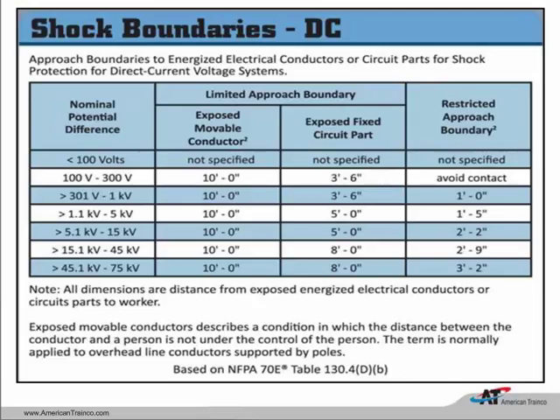And these are both shock protection tables. They have been revised a little bit, especially the biggest one that got taken out was the prohibited approach boundary. Completely gone because it didn't trigger anything. Remember that limited approach boundary triggers no unqualified people. Restricted approach boundary triggers we're going to have all of our PPE on, 1,000 volt rated tools, and the right category of meter. So both of those boundaries triggered something for us, and that's why the prohibited approach boundary was deleted. No trigger for that.